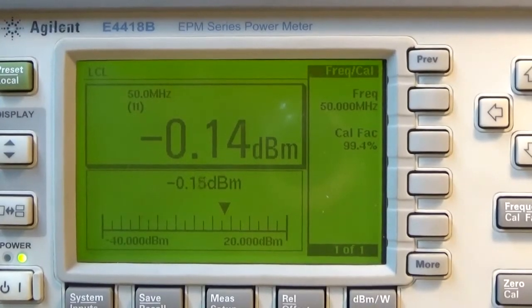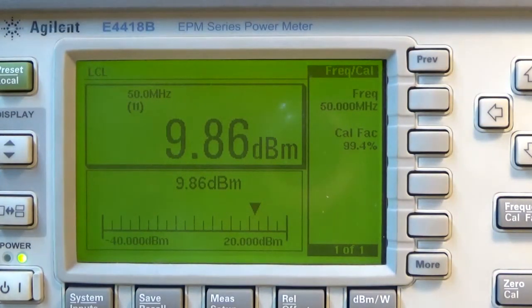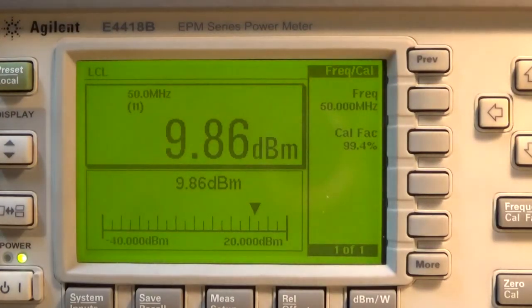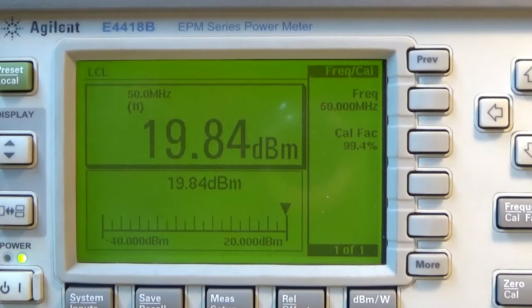Okay, I'm back at 50 megahertz, and I forgot to check above 0 dBm. See what it's like as I go up in power level. So I'll go to 10 dBm, and as you can see my generator is reading 9.86 dBm. Okay, now let's go up to the top of the shop, 20 dBm. My generator will go up to 25 dBm, which is 300 milliwatts, but I'm not going to go any higher than that. So as you can see, 19.85 dBm. So I think that's fairly good for the generator and for the power meter.